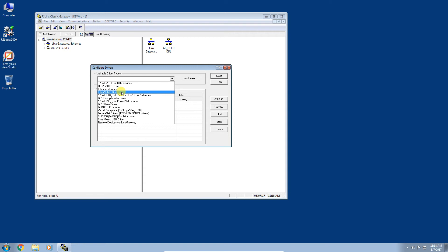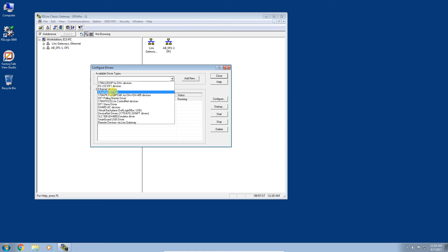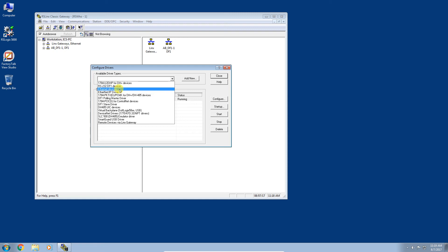There are some differences between these two drivers. If you're connecting to a legacy type controller — for instance, a SLC or PLC5 — you will need to use the Ethernet Devices driver, as those older legacy controllers may not reliably support Ethernet IP. For anything newer, any ControlLogix controllers, you'll definitely want to use the Ethernet IP driver. We'll do both just so you can see the differences. Let's configure the Ethernet Devices driver first.